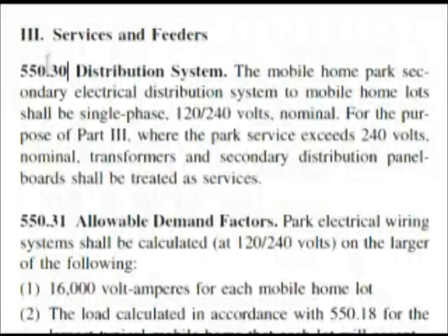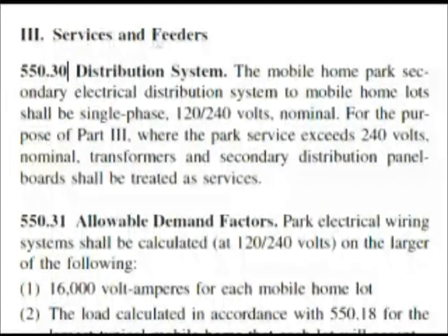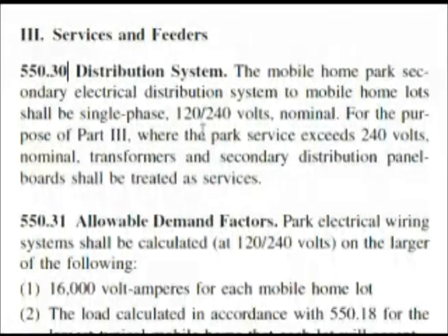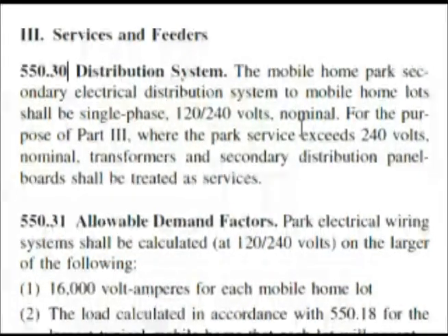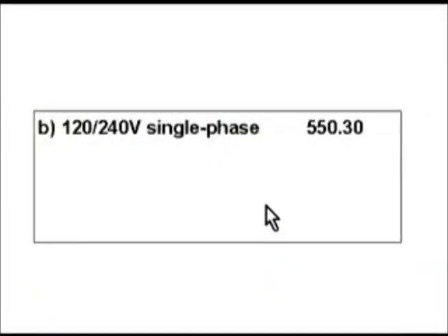So let's go there and look. Here we are at 550.30, and again it's under Services and Feeders for mobile home parks, and it talks about our distribution system. As we read this, it's almost word for word from what we want — it's talking about single phase 120/240 volts nominal, and that was choice B in our answers.